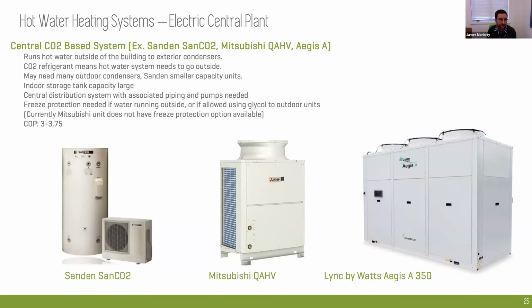Mitsubishi has one, the QAHV, that's come out, making sure there's a freeze protection availability. We are hearing teams are starting to use that, I just don't have exact firsthand knowledge. We have not had teams and engineers get through the frost protection issue, so it's not a unit we've seen. On the CO2 side, we are seeing the one on the right on a couple projects. I suspect, based on the size, the capacity is bigger. I also think it's more expensive. It's trending more toward the commercial size system, both in size but also in cost. So making sure that it fits within the budget of the building is something to keep an eye on there. So those are CO2 systems. Because they're CO2, high pressure, you have to run the hot water out to those units.